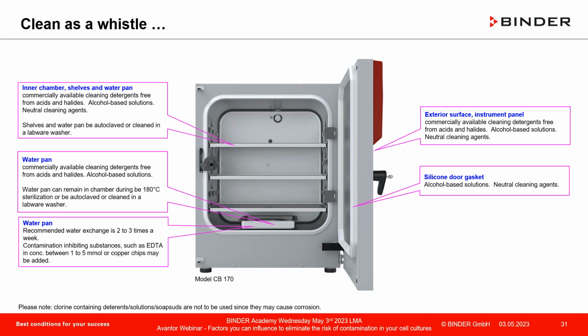The water pan itself, a lot of customer questions reach us asking how often do I have to exchange the water pan? From our side, from the manufacturing side, 2 to 3 times a week. Well aware of the fact that that is not very practical. We have customers where the water is in there for a week or so. Many put in low concentrations of EDTA or a copper chip or something in there to reduce the risk of bacterial contamination. But the more frequently you do that, the lower the risk you will have of contamination. But please open the door quickly and close it quickly again, and make sure that contamination management behavior is in place.